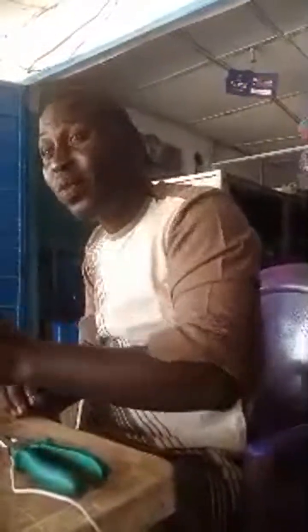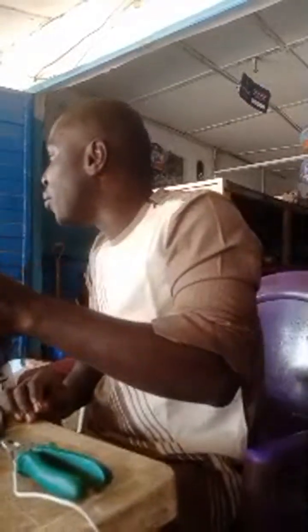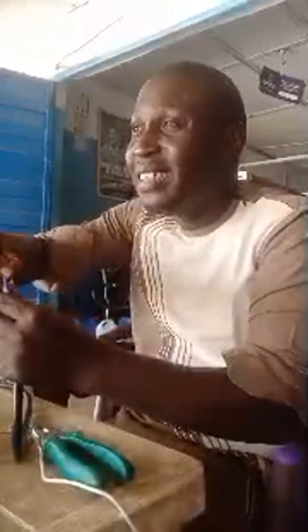You need to note, especially in the environment we are, don't let me say in Nigeria, most times when they say the cable is 6 mm, by the time you put the gauge, it might be like 5.2 or 5. There was a day I and one of my clients went to buy cable, and they were telling him this cable is 15,000, this other cable is 13,000. I was looking at it like, why is it different? If you carry your micro gauge and check it, it might be the thickness of the wire, or the quality of the component of the wire.